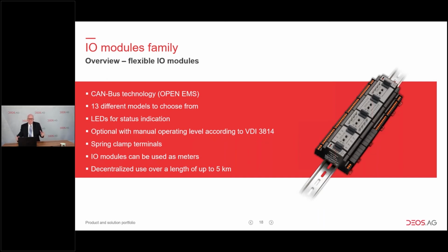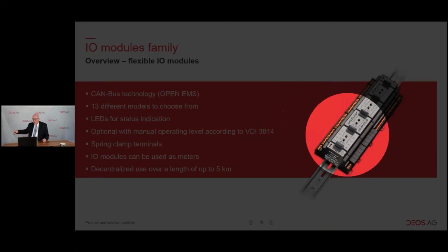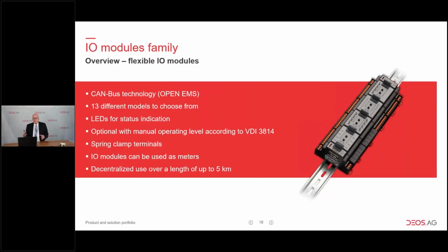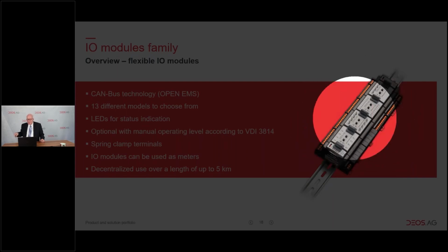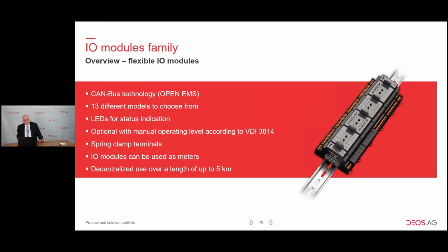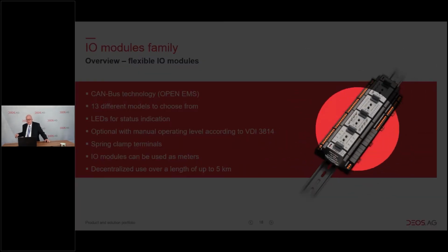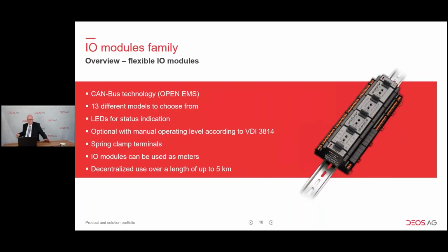The CAN bus has a very high advantage: its range is up to 5,000 meters, so it's possible to install these IO modules up to 5,000 meters away from the controller or control cabinet. So we can place these IO modules in other decentral electrical cabinets, and they have a very nice small size for installation in electrical control cabinets.